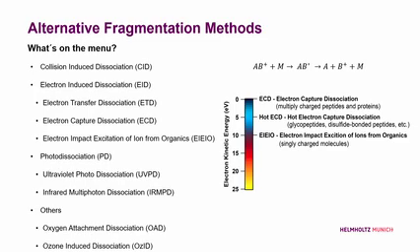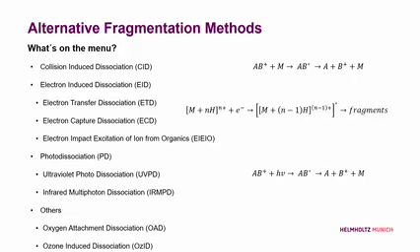This is still a capture type of fragmentation. It's not like you're hitting with electrons and, as with EI, just breaking the bonds. No, it's a capture type of thing. Potentially, once we raise the energies, and you see here we're stopping at 25 electron volts in this illustration from Sciex currently, but if we can go higher, we might reach something that's EI type. But this is an electron capture type of dissociation, just to keep that in mind. So it's not EI, very, very important.